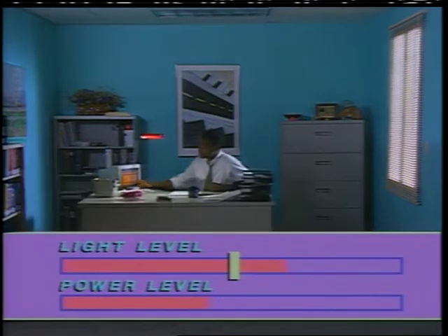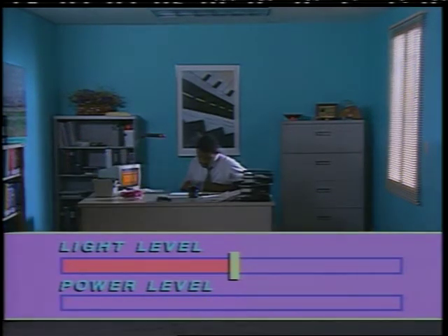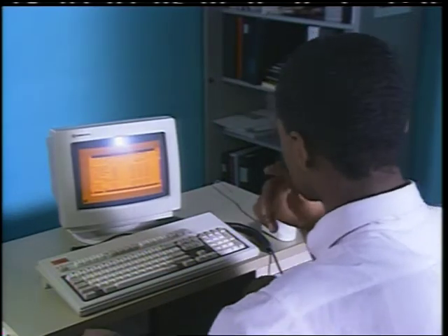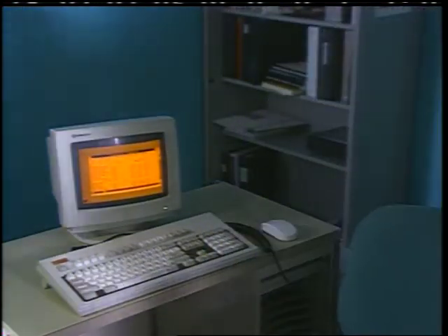In most buildings, the perimeter zone is 15 to 20 feet deep. If rooms are arranged to take advantage of this daylight zone, occupants perceive a high-quality lighting environment and the energy efficiency of the lighting system improves. Making natural light effective inside the perimeter zone takes careful design. Direct sunlight should normally be avoided because of glare and solar heat gains.